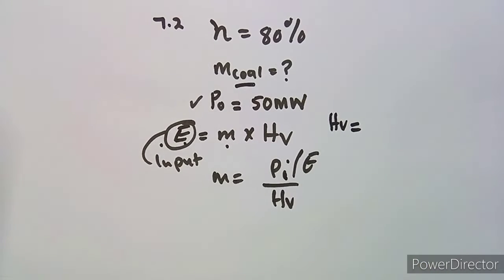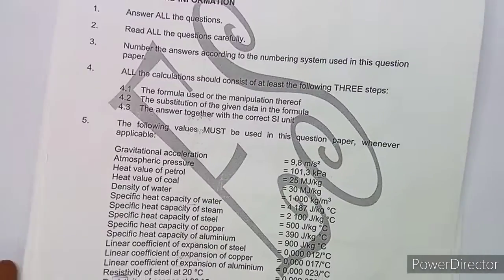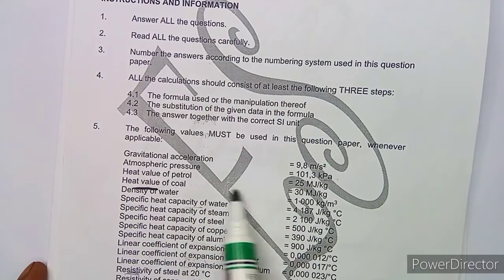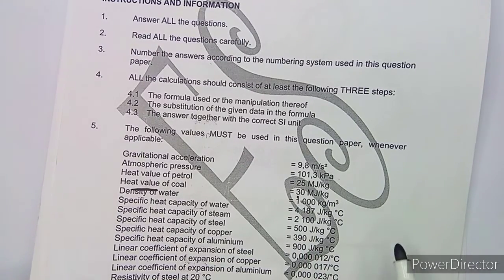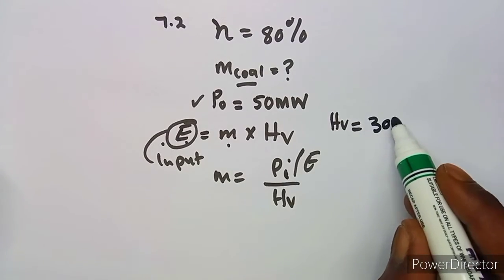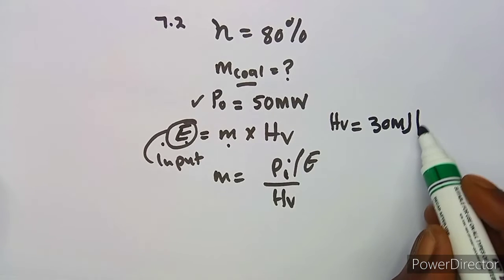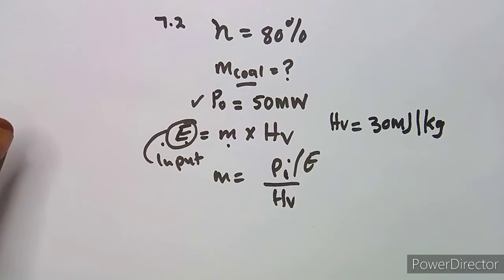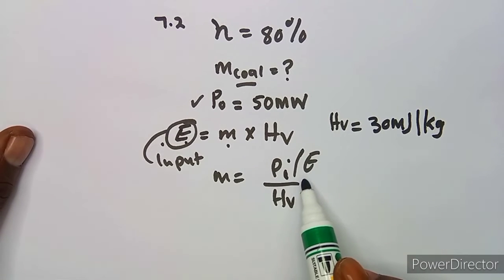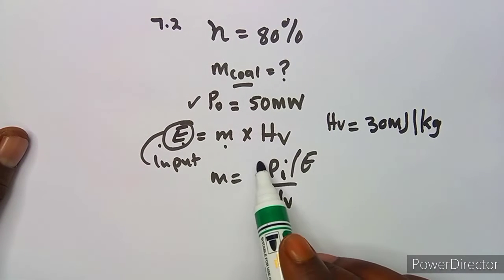We need the heat value of the fuel, which is coal. The heat value of coal is 30 megajoules per kg. So we have 30 MJ/kg. We first need the input power, which we obtain from the efficiency.